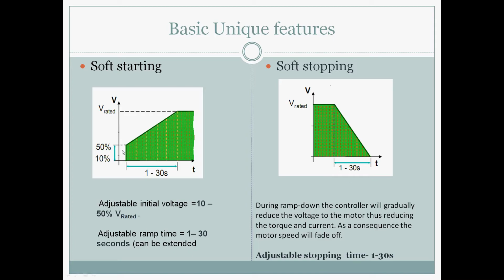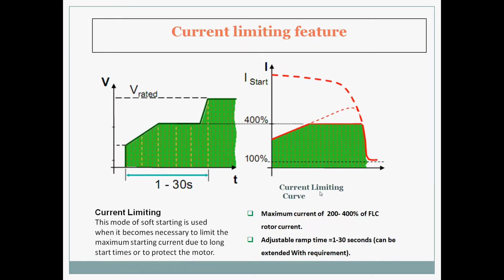First of all, here you can see the voltage at the very beginning is 50%, and then it is gradually increasing from 1 to 30 seconds. It is a given time. 50% rated voltage is given as the initial voltage, and then the ramping up time with a proper time basis. And again with soft stopping, the same thing happens. Voltage goes from rated voltage to zero voltage, ramping down by the controller, gradually reducing the voltage to the motor, thus reducing the torque and current. As a consequence, the motor speed will fade off. Adjustable stopping time for a standard soft starter is 1 to 30 seconds.